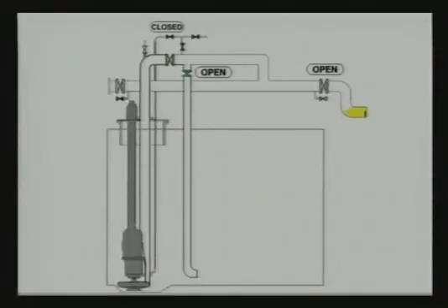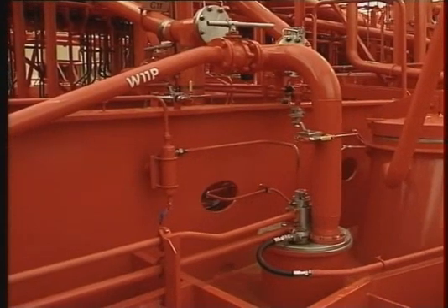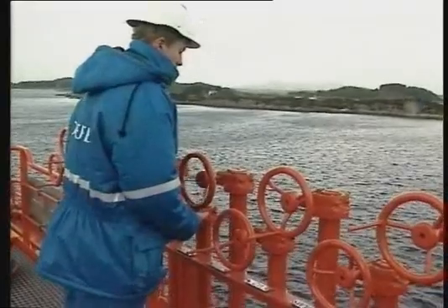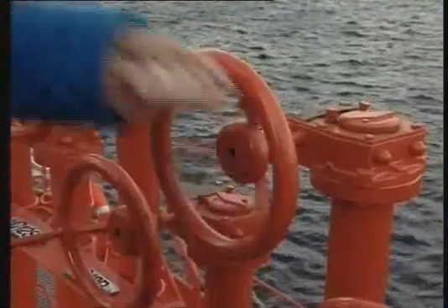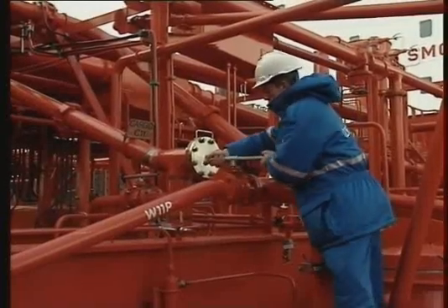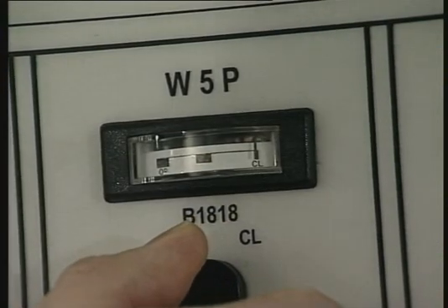This is a recommended cargo pipe layout in the Framo system. If bypassing is not possible due to valve arrangement, use the following procedures to avoid pressure peaks in the cargo piping during loading. Keep the manifold valve closed until the cargo reaches the manifold. Open the manifold valve partly to fill the cargo line on deck. Open the cargo drop line valve and pump discharge valve slowly until you reach maximum capacity. Remember: maximum loading pressure is 8 bar, measured at the top of the pump.